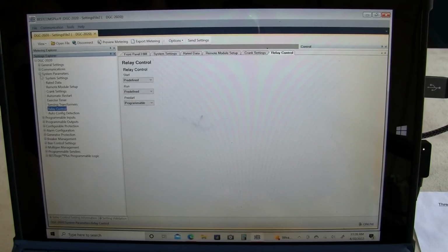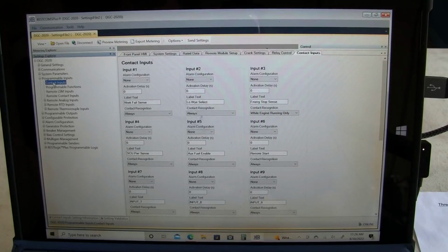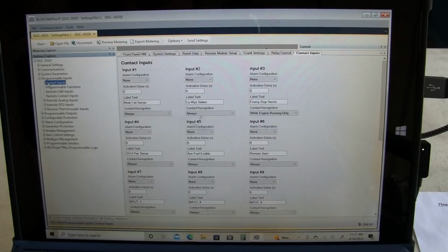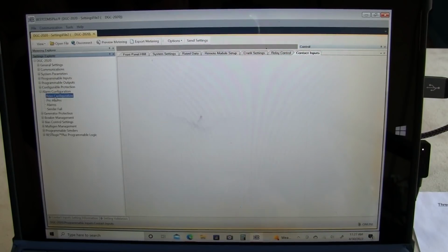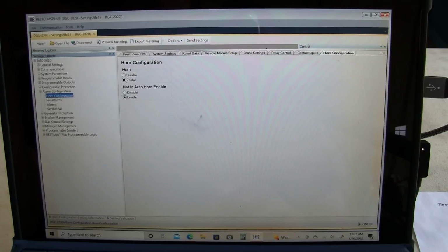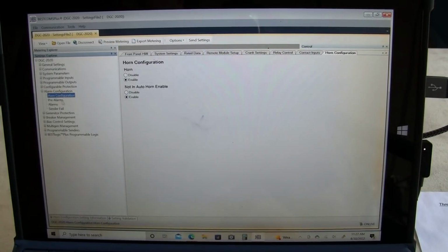Let's see. What's next? Programmable inputs. We got a couple of those. We don't need that. We'll just skip over that for right now. Outputs. Alarm configuration. That's the next important one. Horn configuration, which is the audible alarm. We have it enabled, and we have it enabled when the controller is not in auto.